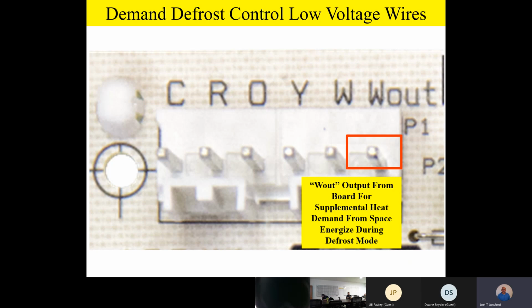Now, you remember I mentioned there was a relay on board out there. So the W and the W out loop through a normally closed relay. But now watch this. When it goes into defrost, that relay switches, click, and then it takes the Y signal. In other words, the compressor has to be running during defrost. So during defrost, it takes the Y signal and loops it out through W out. And so that's the main difference that we've got to remember: during defrost, our power source for the W out is actually the Y terminal.